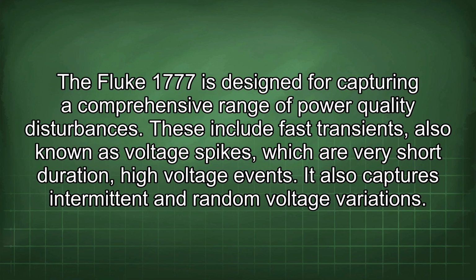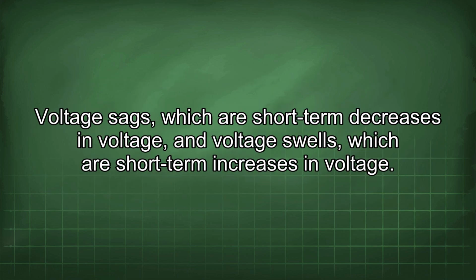The Fluke 1777 is designed for capturing a comprehensive range of power quality disturbances. These include fast transients, also known as voltage spikes, which are very short-duration high-voltage events. It also captures intermittent and random voltage variations. Voltage sags, which are short-term decreases in voltage, and voltage swells, which are short-term increases in voltage.